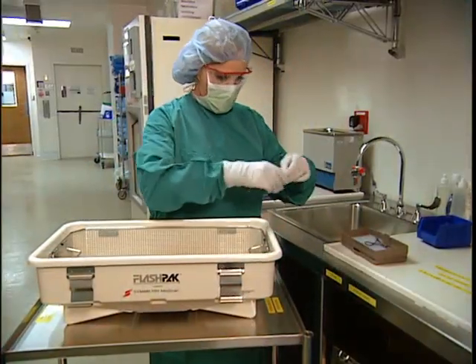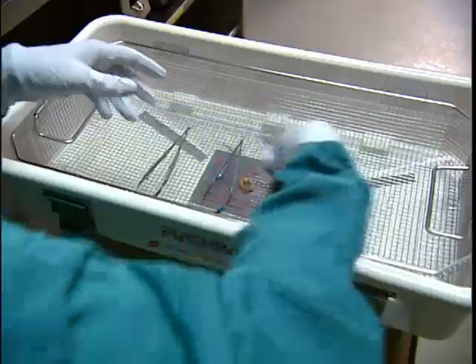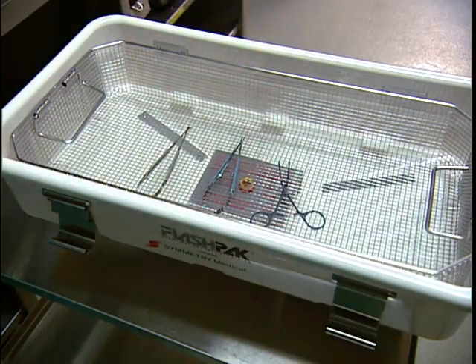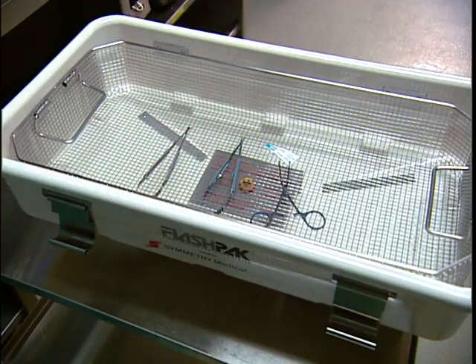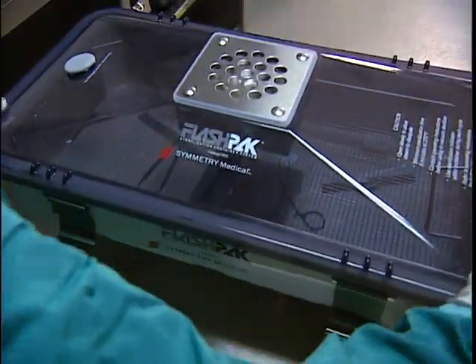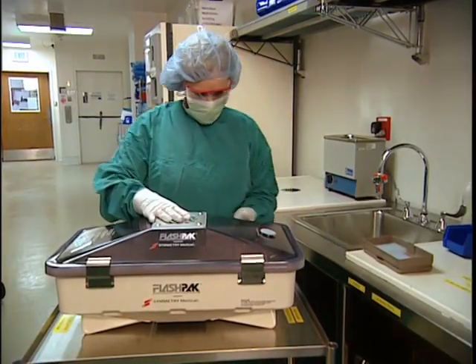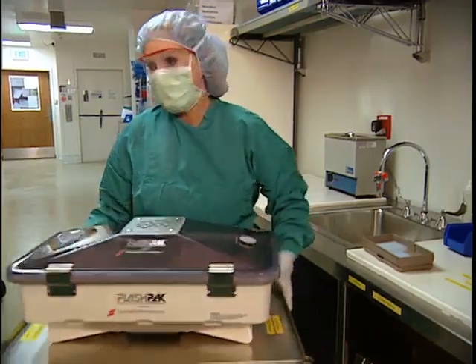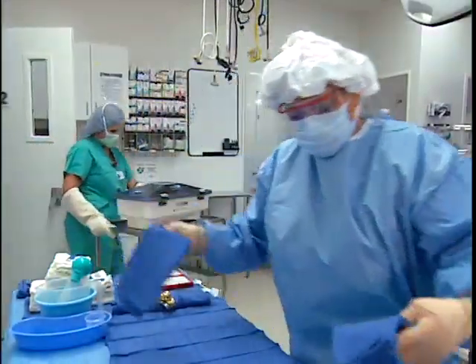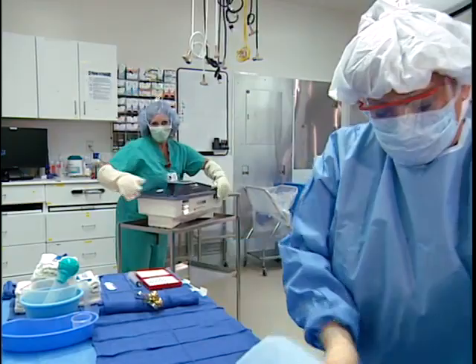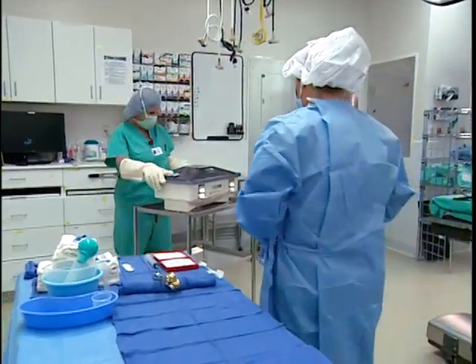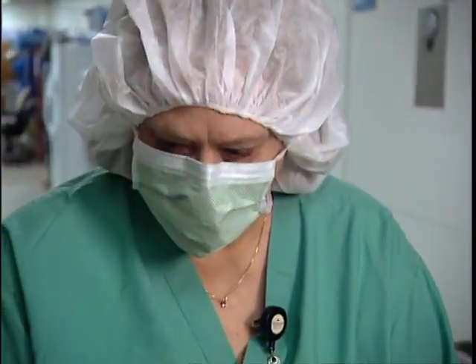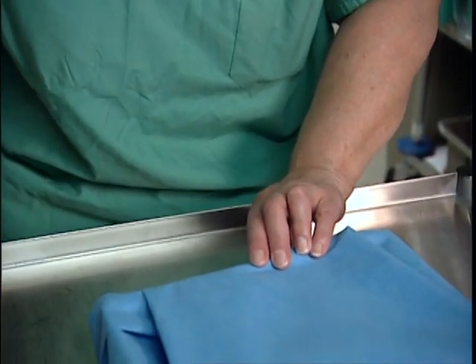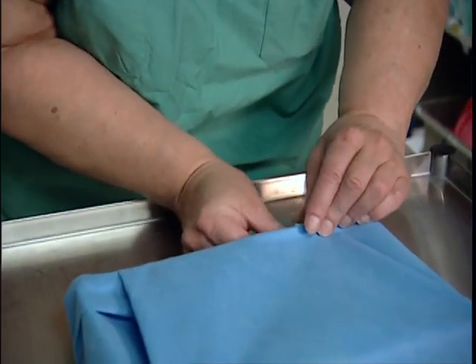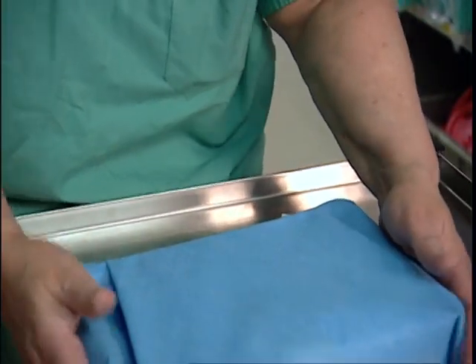Place clean items in a rigid, closed sterilization container or tray designed and labeled for immediate use steam sterilization in a manner that allows steam to contact all instrument surfaces. Rigid containers will also protect sterilized items during transport to point of use, as well as facilitate ease of presentation into the sterile field. For express sterilization, use packaging recommended by the sterilizer manufacturer, such as single-ply, non-woven wrappers that are compatible with the process.